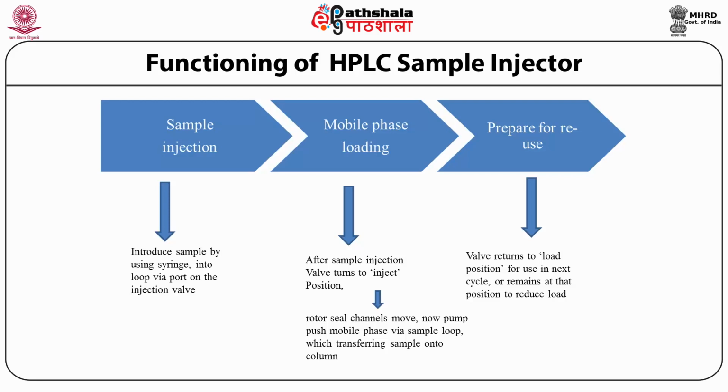The needle is raised again to move the vial away. When the needle is lowered again, the air actuator reverses the valve and the sample loop is reconnected to the mobile phase flow. When the sample is completely discharged into the column, the motor moves the syringe plunger to the end of the syringe, disposing the remaining solvent.